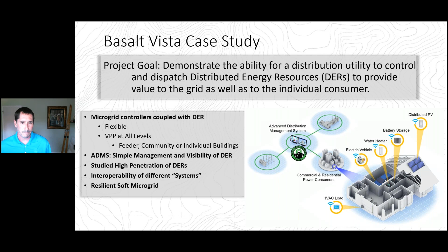By the end of the day, what we had built was a resilient soft microgrid. It's a house that's able to microgrid by itself, but the 4 homes aggregated together work better to perform grid functions. We call it a soft microgrid because it has the ability to microgrid, but it works better when it can get the pulse from the grid, the frequency and the voltage. When it has those two and doesn't have to synthetically make it on site, it's able to perform at a much more economic scale.